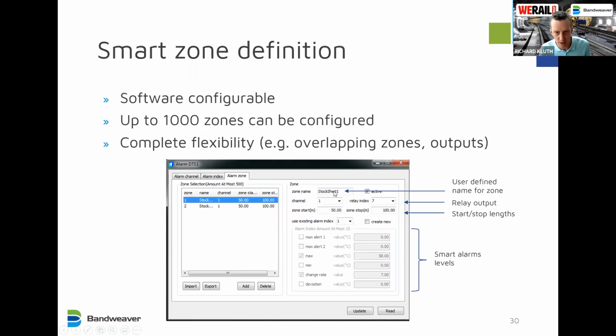So this is a screenshot of the software, it just gives you an idea of how these alarms are configured. So this is the details for a zone. You would give the zone a name, something intuitive, or the name that corresponds to the one on the fire panel, which optical channel, which relay is activated, where it starts, where it stops, and then all the different temperature smart alarms that you put in there. And you can have multiple alarms for a zone, so it's very powerful.